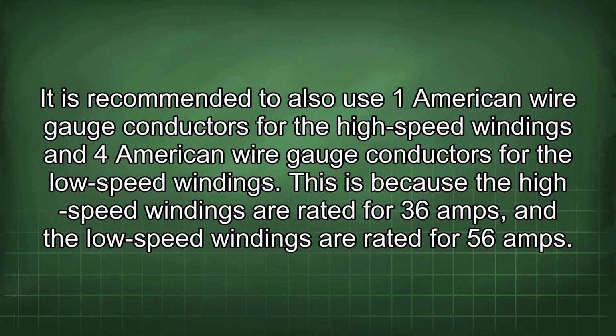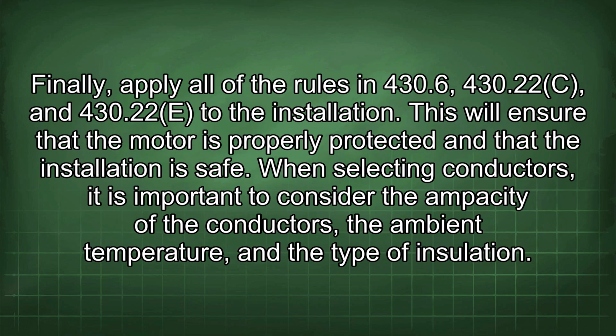It is recommended to also use 1 American wire gauge conductors for the high-speed windings and 4 American wire gauge conductors for the low-speed windings. This is because the high-speed windings are rated for 36 amps, and the low-speed windings are rated for 56 amps. Finally, apply all of the rules in 430.6, 430.22c, and 430.22e to the installation. This will ensure that the motor is properly protected and that the installation is safe.